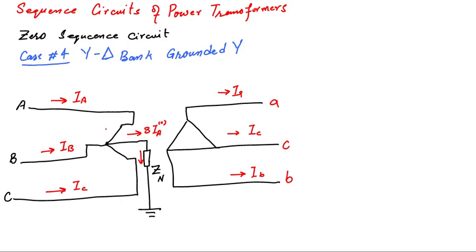Actually, what is happening here is that the counterpart of the zero sequence current which is flowing through these three windings will exist in the form of circulating current within the delta. Although that zero sequence current will not be able to come out of the delta, it may exist in the form of circulating current within the delta. So it means we have a path only from one side for the flow of zero sequence, that is from the Y grounded side of the transformer.